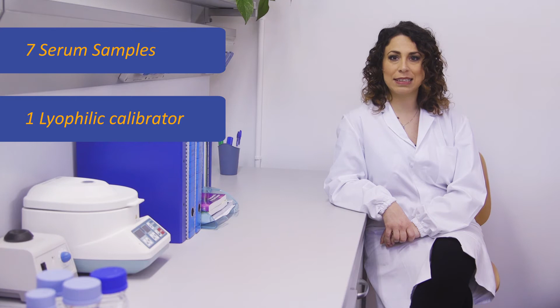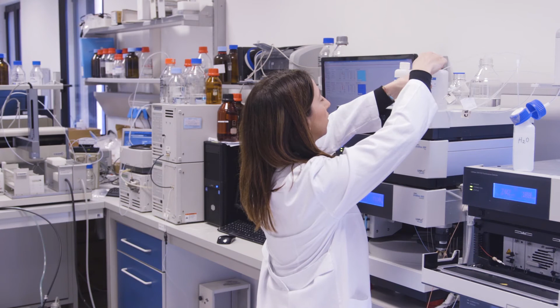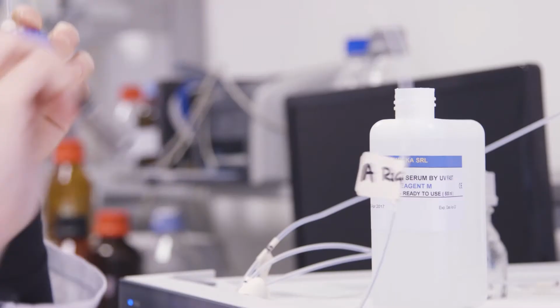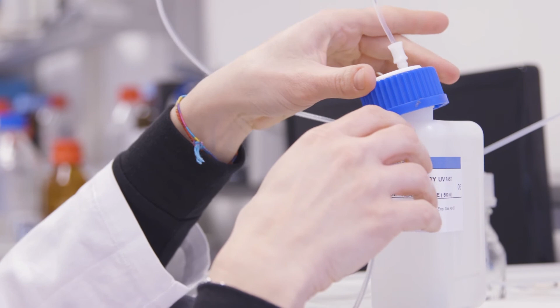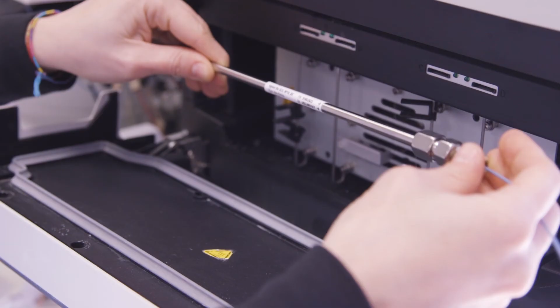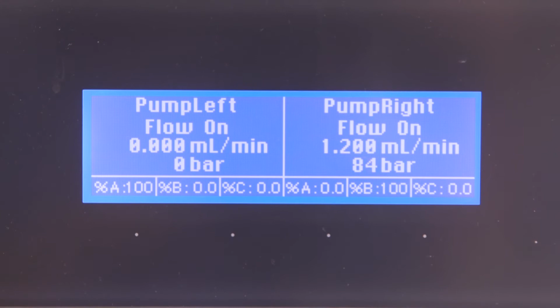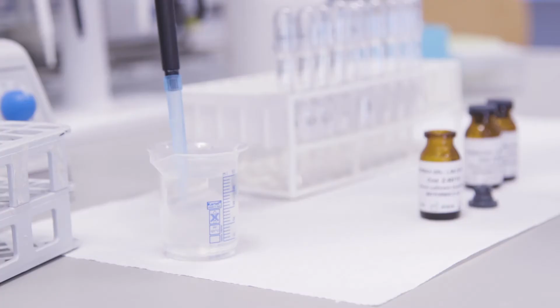First, we prepare the HPLC. The instrument must be cleaned from the previous analysis. We put the HPLC grade water into the pump and let it flow into the system so that the tubing is flushed. This is important because the column mustn't come into contact with the organic solvents. Washing the needle is also done with water and not with organic solvents. After being primed with water, we can continue by inserting the mobile phase, reagent M, into the pump spout, mounting the column and flushing at 1.2 ml per minute for 30 minutes.